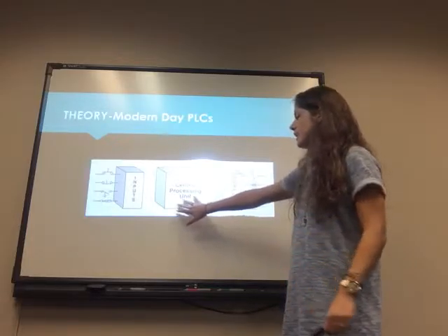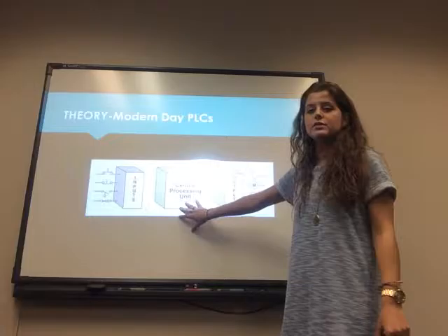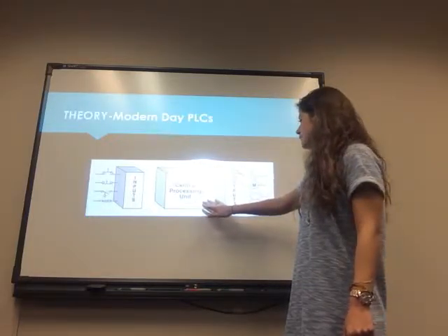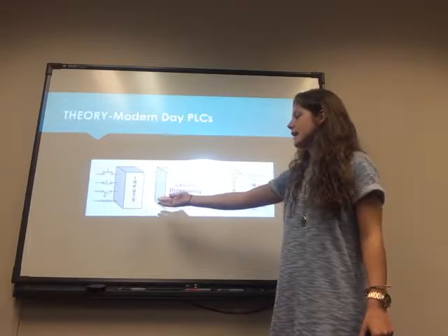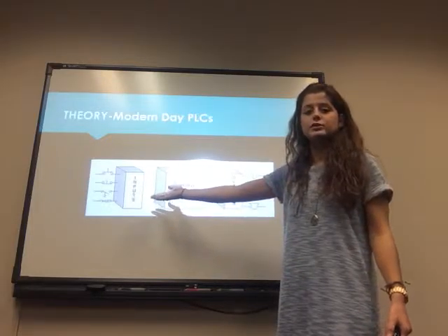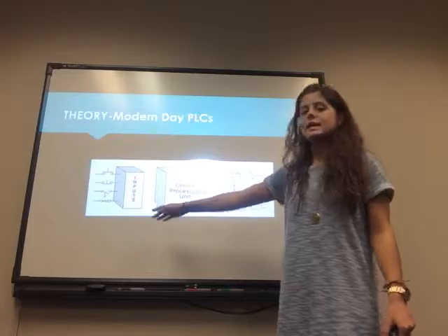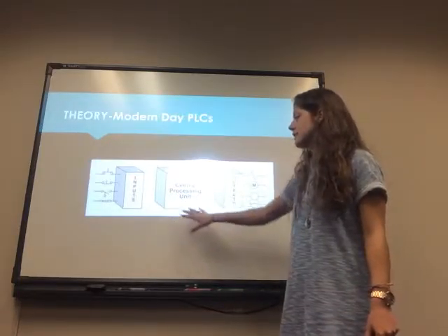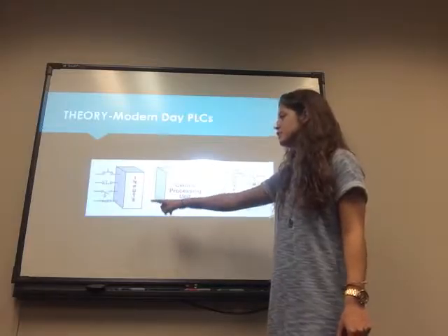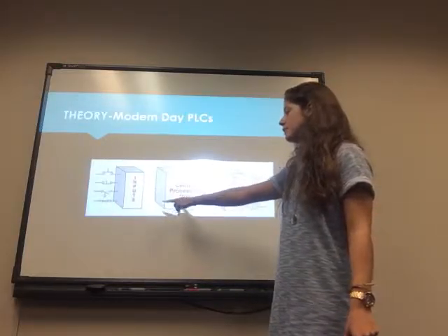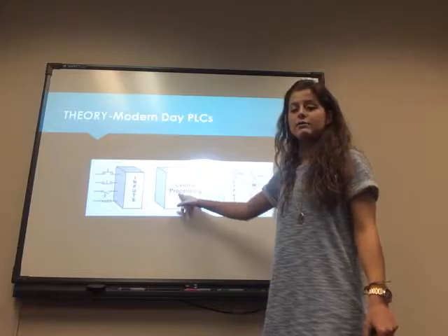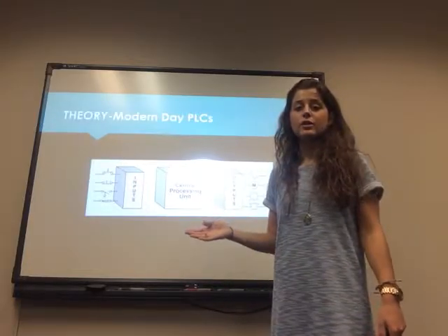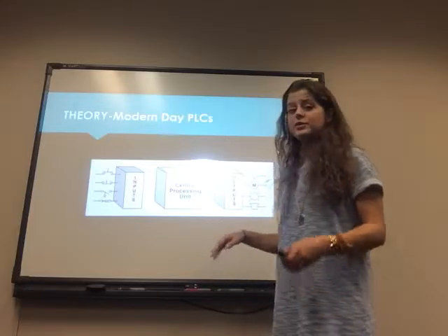The program scan, the second part, is essential, and this is where all the logic resides. For example, if it is a voltage reader as an input scan, and it hits, let's say, 10 volts, and an alarm is supposed to go off, the program scan has to read in the 10 volts and then know that, oh, 10 volts is too much, and so then trigger the alarm on the output. And the fourth part is called housekeeping, which is communication between the terminals.